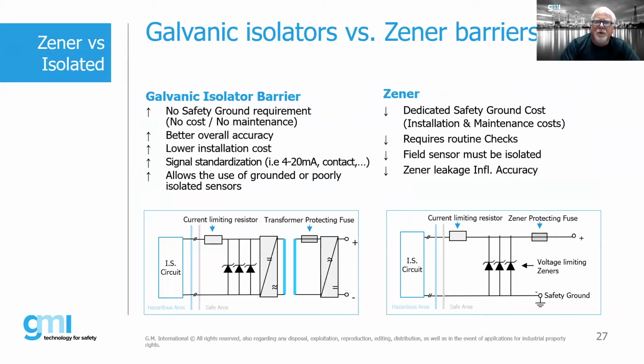So, a couple of pros and cons, because I know this is always a question that people have. As I mentioned, with the galvanically isolated barrier, there is no grounding requirement, so it can reduce the installation cost. Installation cost has to do with the fact that I don't have to worry about how I'm going to tie a ground into it, or whether I've got an energized bus system, or however I'm going to do it. It also allows the use of grounded or poorly isolated sensors. This is an issue when you have a lot of noise or some potential issues.